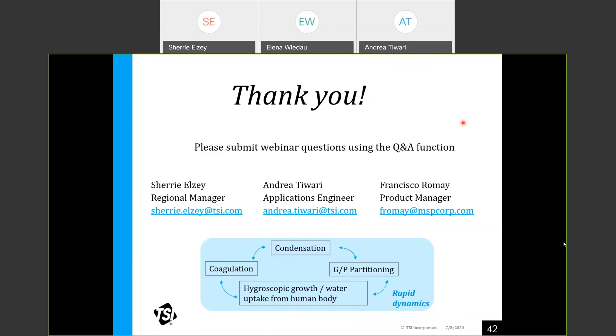Another question: how are particle sizes binned by the SMPS — what is the actual size range within each reported size? The reported sizes are midpoints of the bins, and the bins are spaced evenly on a logarithmic scale. For more detail, please refer to the application note or contact us via email.